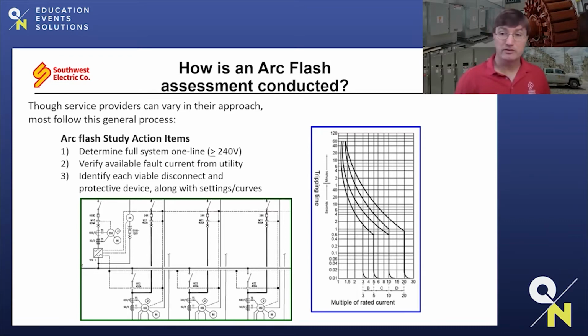We need a lot of data, thousands and thousands of data points that we need to essentially replicate the electrical distribution system within a given facility and model it into a computer. So this involves getting all the one-line diagrams, electrical drawings of that facility. It involves verifying what the fault current levels from the supplying utility could possibly be, as well as documenting all the various different data points throughout the system, all the equipment, all the protection, all these settings. This process could take days, weeks, possibly months, considering how large your facility or your campus is.